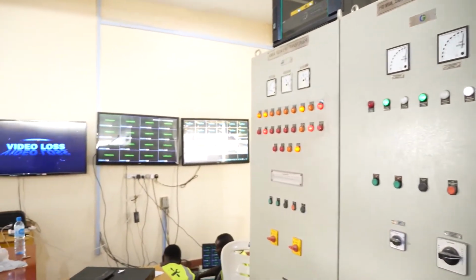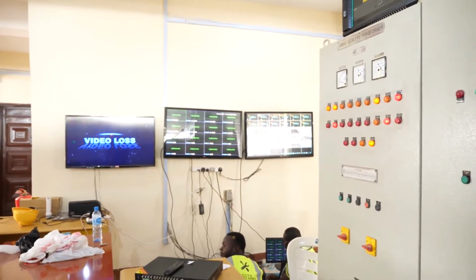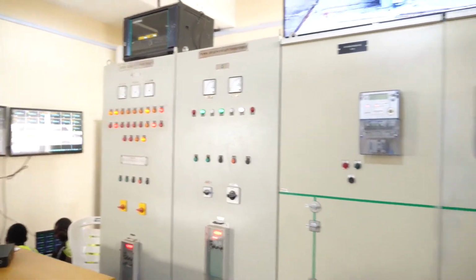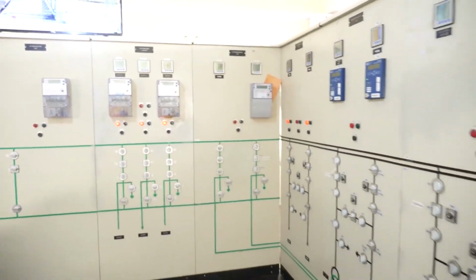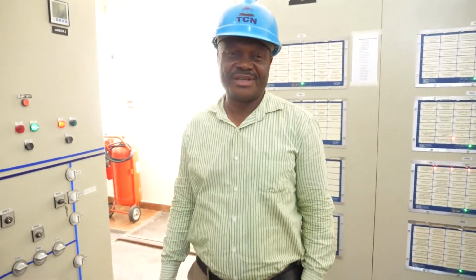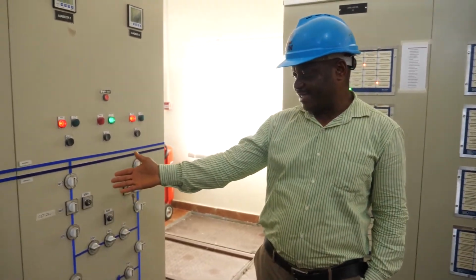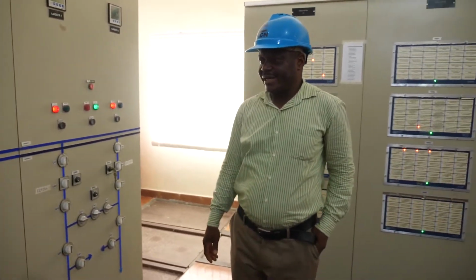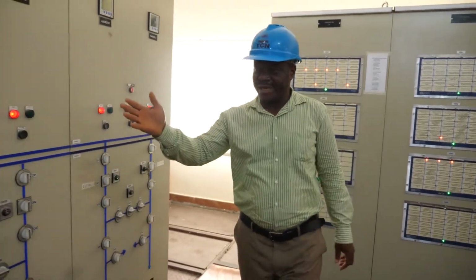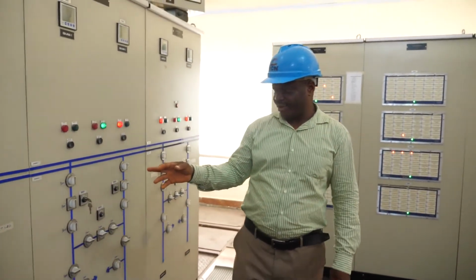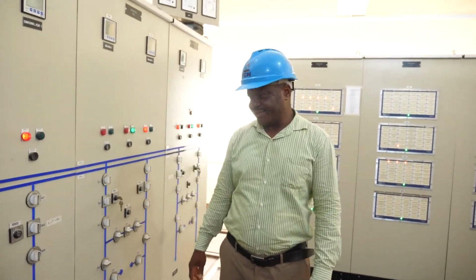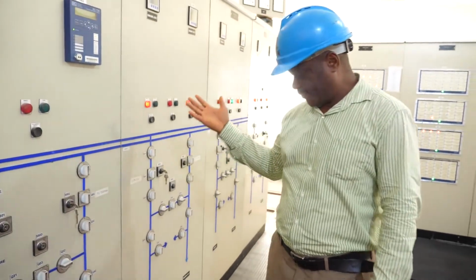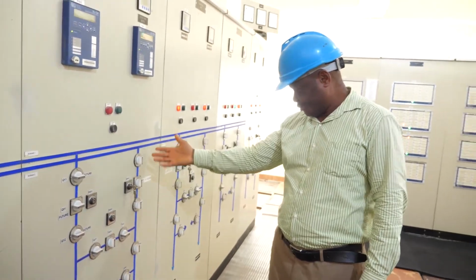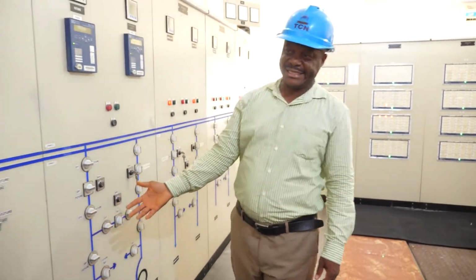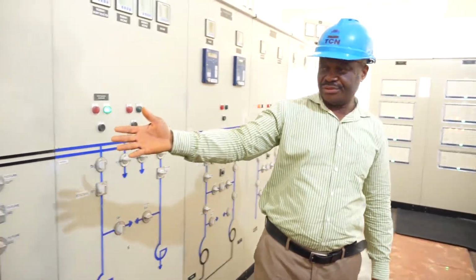In the control room of the 330/132 kilovolt Lokoja transmission substation, the substation supervisor spoke more about the source of bulk power supply to the substation as he explained the components of the control room. We have a source of supply from Ajaokuta, double circuit, line 1 and line 2. Line 1 is J1L and line 2 is J2L. The outgoing lines are Gwagwalada line 1 and line 2, line 1 circuit L6G, and line 2 circuit L7G. We have one number 150 MVA that's connected to bus bar 2, and we have one number 60 MVA that is connected to bus 1.